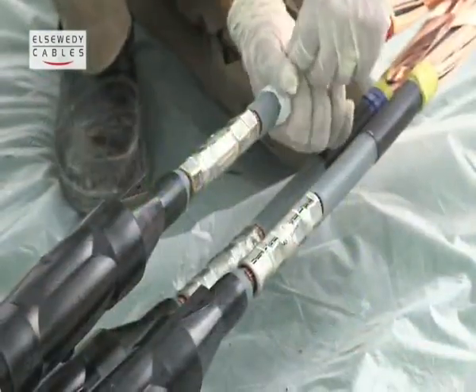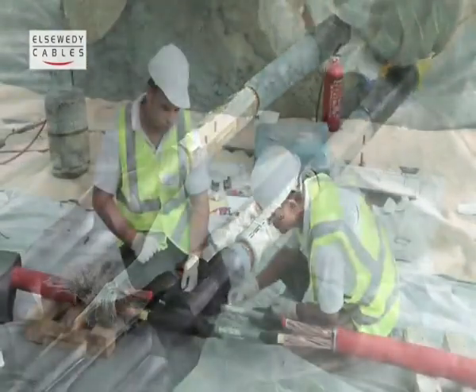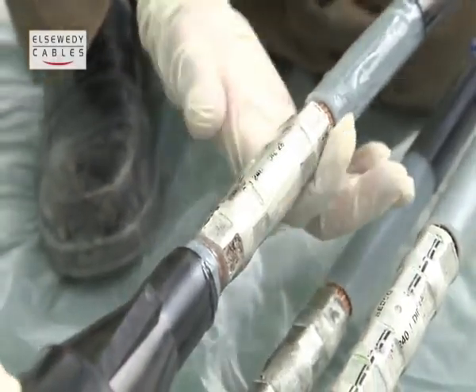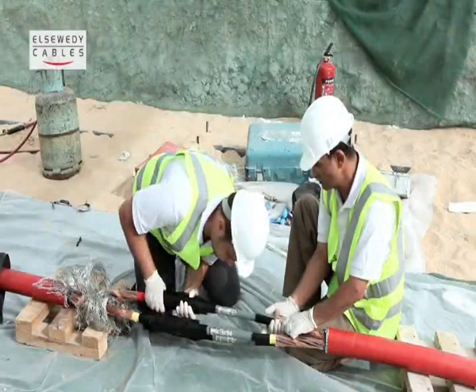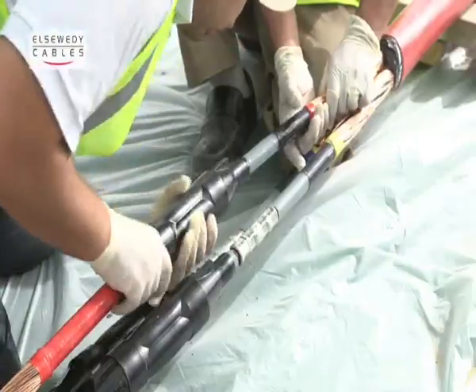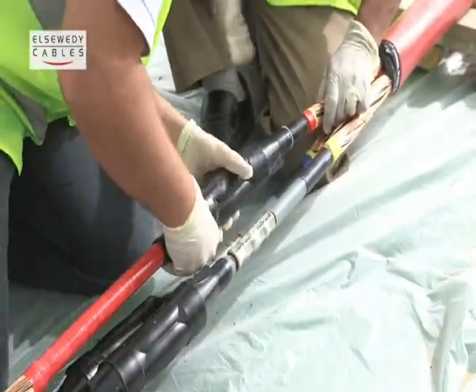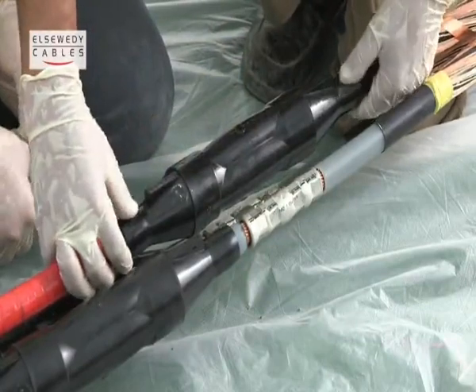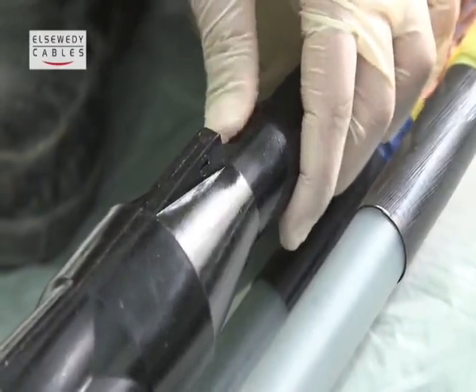Clean and lubricate all insulation of the short-sided cable cores. Slide the housing by pushing and slightly twisting into its final position. Proper positioning is ensured by observing and equalizing the deformation of joint ends caused by the underlying edge of the outer semi-conductive layer.